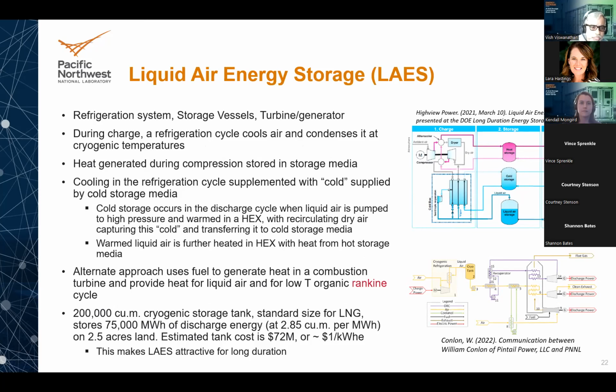A liquid air energy storage system. Essentially, it has a refrigeration system for charge, storage vessels for storage, and obviously a turbine generator for discharge. During charge, a refrigeration cycle cools the air and condenses it to cryogenic temperature. Heat generated during compression is stored in the storage medium. On the right, upper right, you see a heat storage in red. That's where the heat is stored. Cooling in the refrigeration cycle is supplemented with cold supplied by cold storage medium. Just below the hot storage, you see the cold storage medium tank.